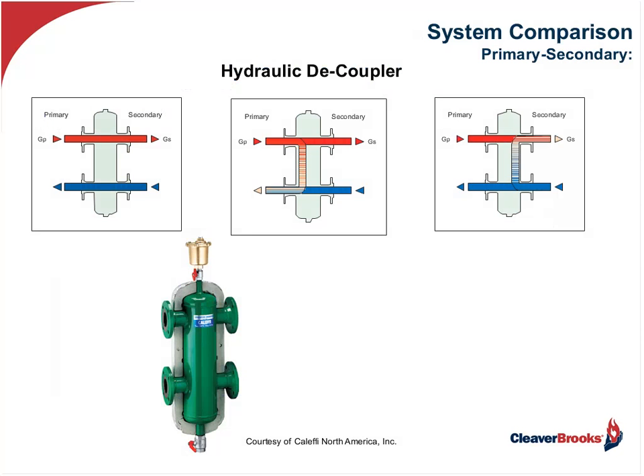Now the decoupler, and here's a picture showing what happens in a decoupler. A decoupler can be as simple as just a piece of straight pipe with multiple connections. Its purpose is to provide hydraulic separation between the primary pumps and the secondary pumps so that the pumps do not affect the other pumps' operations. If the flow is matched, as you see in the first graphic here, the water simply flows through and there's no interaction between it. If your primary flow or your boiler flow rate is higher than your secondary or system flow rate, you're actually going to bring water back around, and this will cause the temperature to the boilers to increase, and we'll give you lots of examples of that in a few minutes.